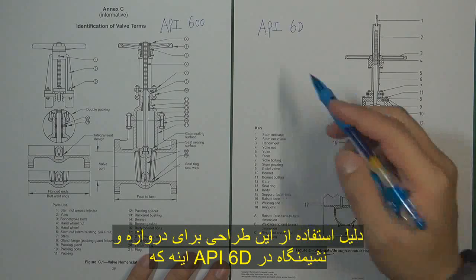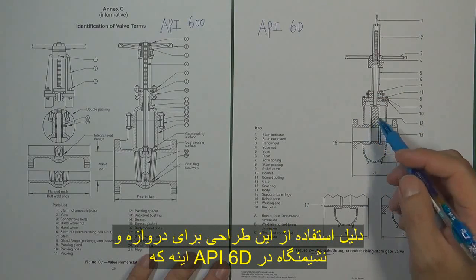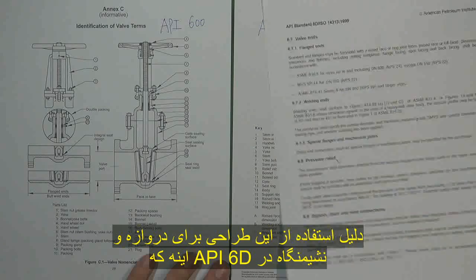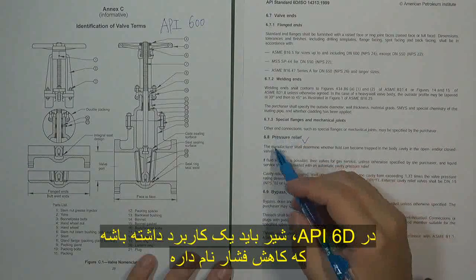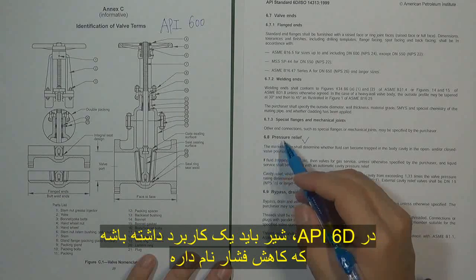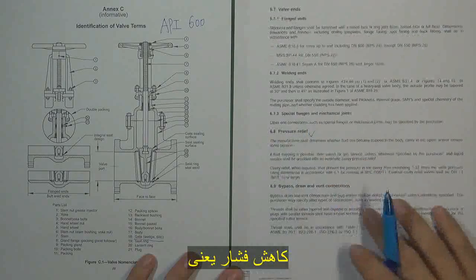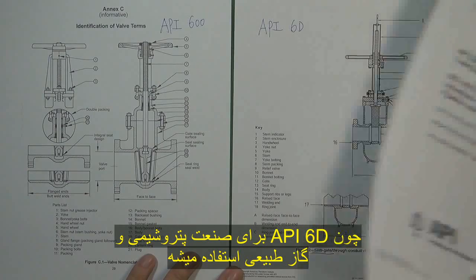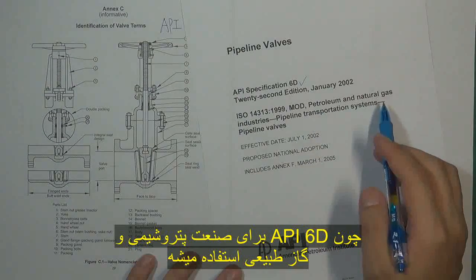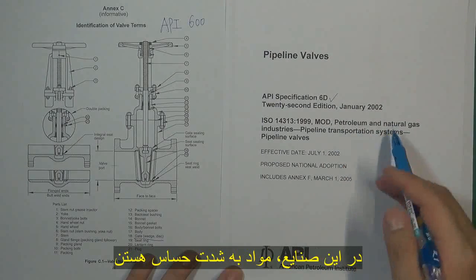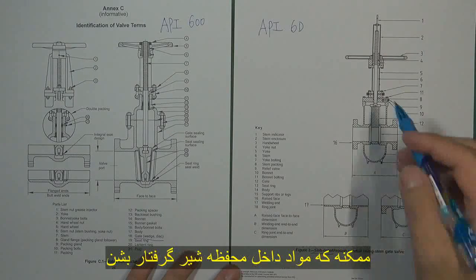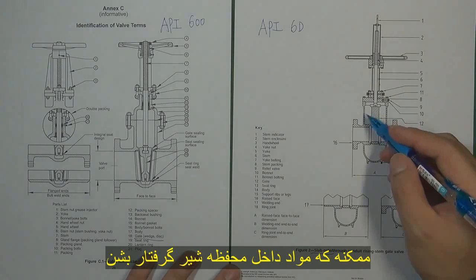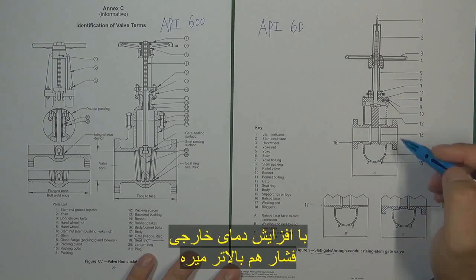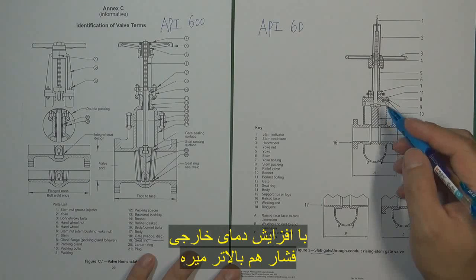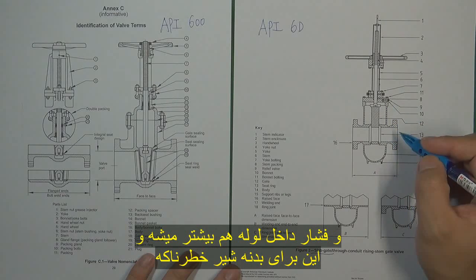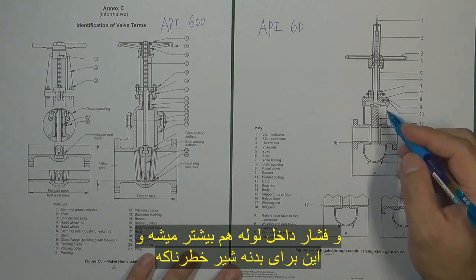The reason why the API 6D uses this kind of design for the valve gate and the valve seat is that in API 6D, the valve must have one kind of function, which is called pressure relief. The pressure relief is needed because API 6D is for valves working in the petroleum and natural gas industry. In this kind of industry, a lot of flow media are very sensitive. The flow medium can be trapped inside the valve cavity. With the outside temperature going higher, the inside pressure also goes higher, even higher than the pressure inside the pipe. So that will be very dangerous for the valve body.